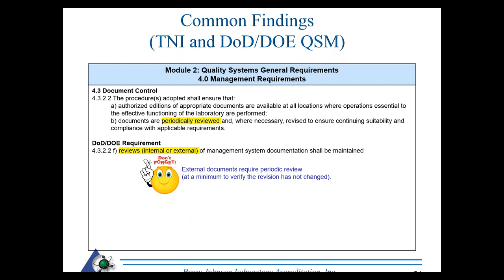External documents that support activities must also be part of the quality management system and fall under the periodic review requirement. This means verifying at minimum that no new revisions have been issued. If your quality management system has been verified to meet a specific revision of an external document — a PJLA policy, test method, or other source — you need to show you've verified no new revision exists, to confirm your system remains compliant with the most current version.